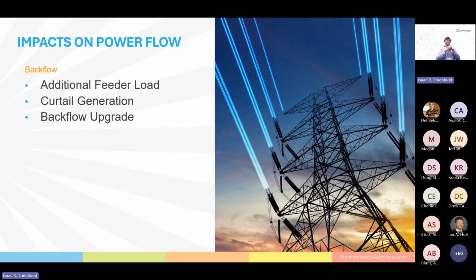So, impacts on power flow. As we previously covered, historically, distribution systems flow in one direction, from their sources, often the transmission substation, to their loads. Distributed energy resources not only shift this paradigm, but do so dynamically. When a distributed energy resource's generation exceeds the load on the feeder, it will cause a backflow condition that can cause damage to equipment or cause nuisance trips for protective equipment unprepared for a backflow condition.